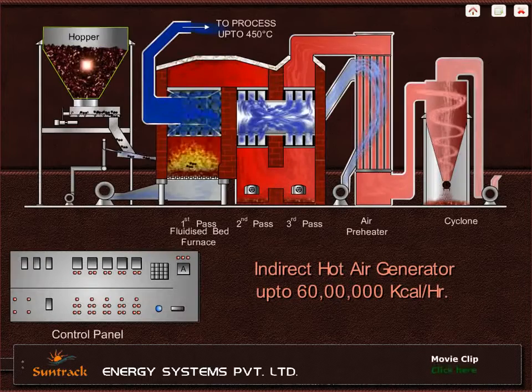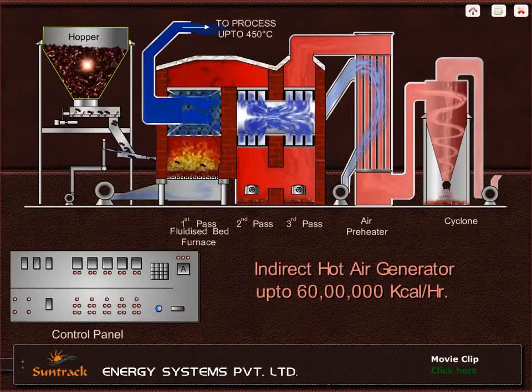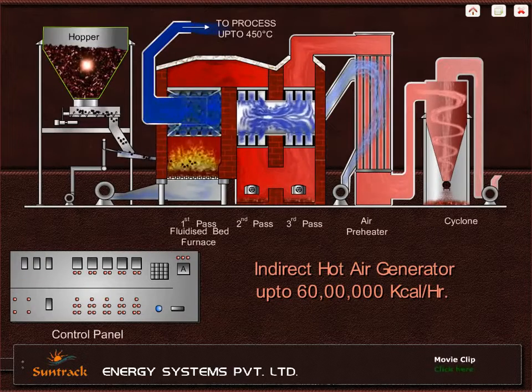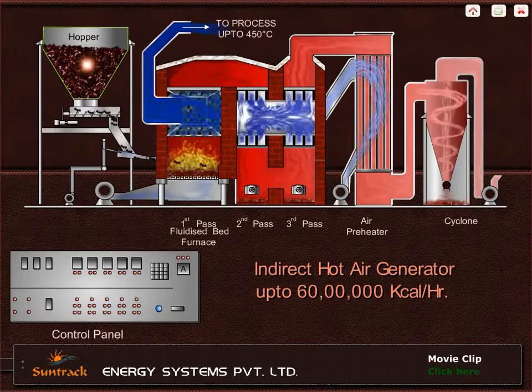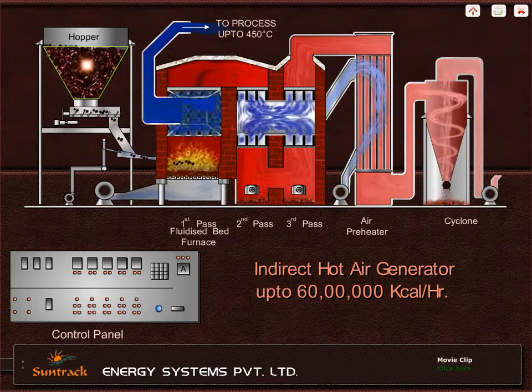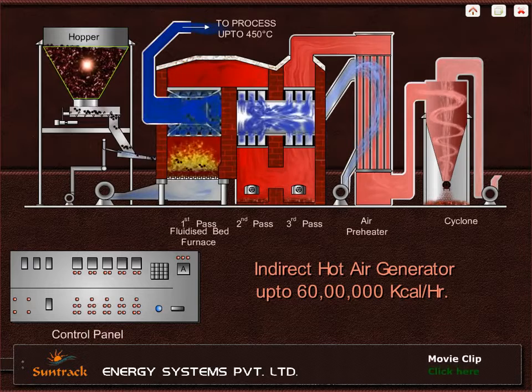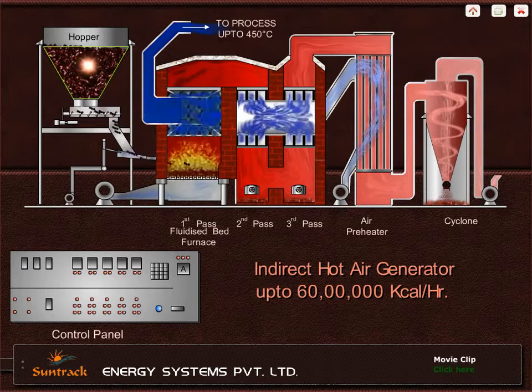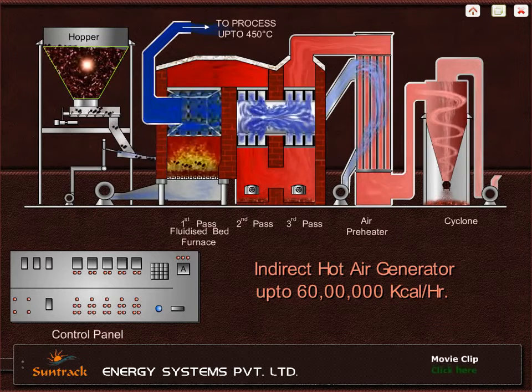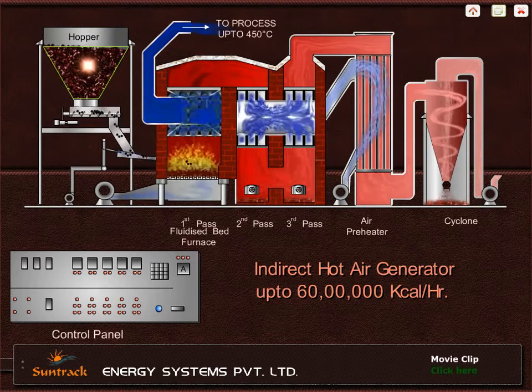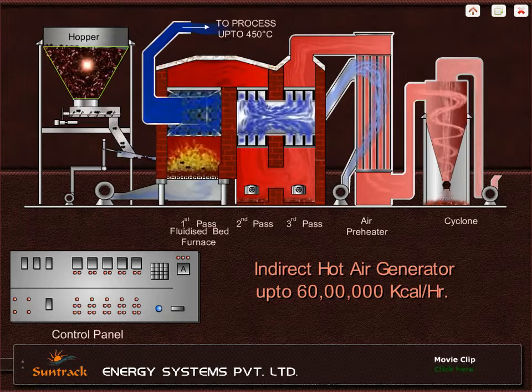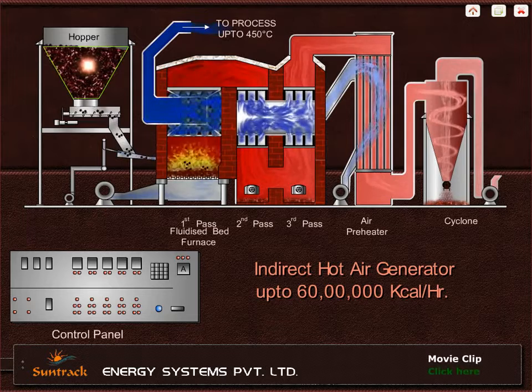The hopper provided has the capacity of about 8 hours of lignite or steam coal. Fuel having particle size below 4 mm is filled by a suitable material handling system. The same hopper stores about 3 hours of agro-wastes.